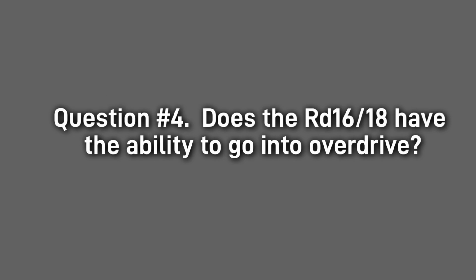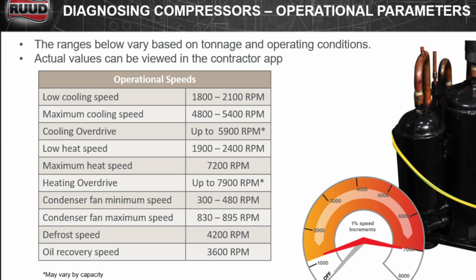Question number 4. Does the RD16 and RD18 have the ability to go into overdrive? The system's overdrive capability provides approximately 9 to 10% increase in compressor RPM beyond normal maximum operating speeds, both in cooling and heating modes. It's important to note that these values can vary depending on tonnage and operating conditions, and actual system performance data should always be verified using the contractor app. In addition, when the system is controlled with a standard 2-stage thermostat, you won't achieve the full benefit of overdrive functionality.